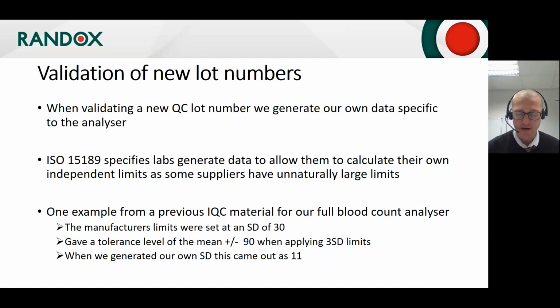ISO 15189 specifies that laboratories generate their own data to allow them to calculate their own independent limits, as some suppliers from experience have unnaturally large limits. This might be in order to cover the wide range of analyzers and suppliers that are the target market. One example of this was some IQC material for a full blood count analyzer. The manufacturer's limits were set at an SD of 30.